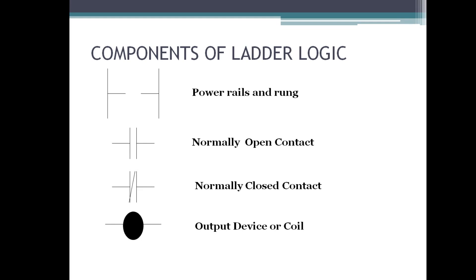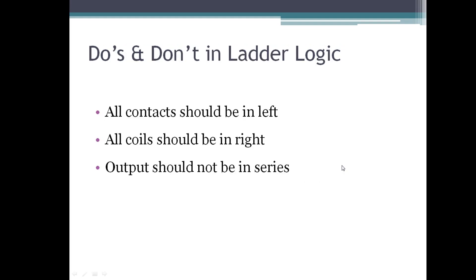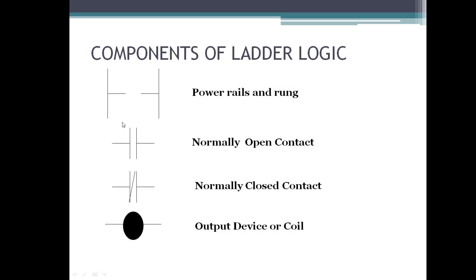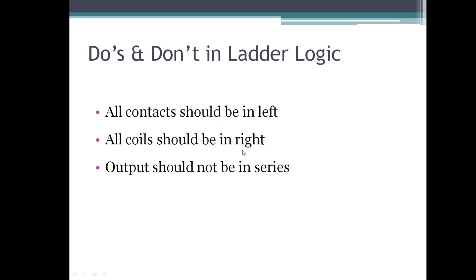Now let's look at the do's and don'ts in Ladder Logic. The two vertical lines are the left and right sides — all inputs should be connected to the left side only. The rung must end with a coil on the right side; ending with an input will cause an error. The coil should be on the right side, and the output should not be placed in series — each rung should have only one output. Remaining do's and don'ts will be explained in the software.